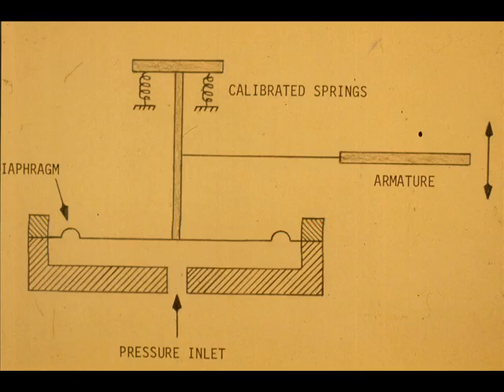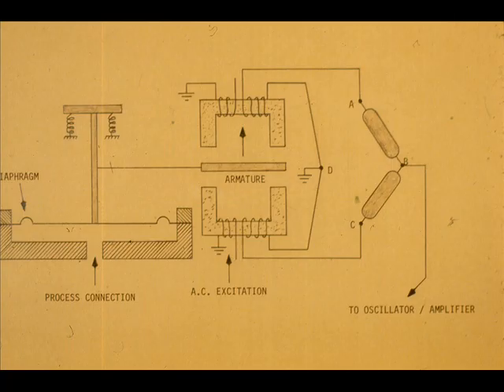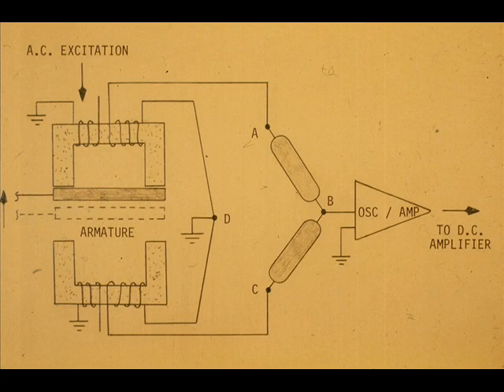An armature attached to the stem will facilitate magnetic detection of the armature position caused by any diaphragm movement. In this type transmitter, the total movement for the diaphragm and the armature is approximately 0.0025 inches for the complete range measured. An increase in pressure will move the armature upward, thus increasing the voltage at point A in the bridge ABCD. The voltage at point C will be decreased. The changes in voltage at points A and C are the result of the change in reluctance caused by the movement of the armature.